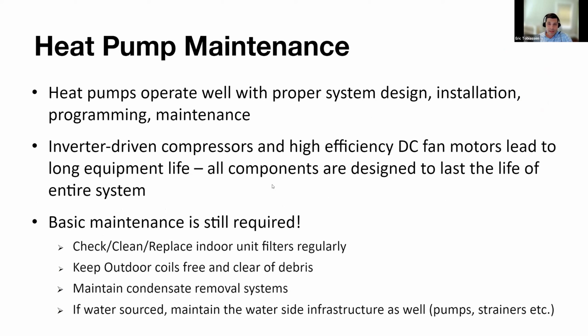Heat pump maintenance, it's really set it and forget it. The main thing with heat pumps is a good install. So you're pressure testing your piping lines, you're vacuuming out any contaminants that could be in the system. Heat pumps have inverter driven compressors and high efficiency DC fan motors, and this is all going to lead to long equipment life. All the components are designed to last the life of the entire system, which is typically around 20 years, is what I've heard. But basic maintenance is still required.